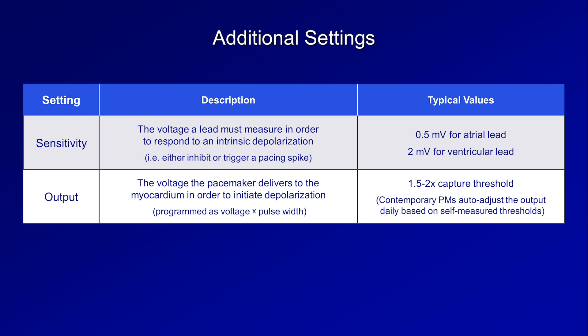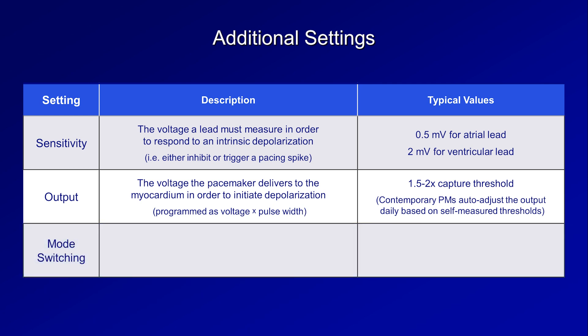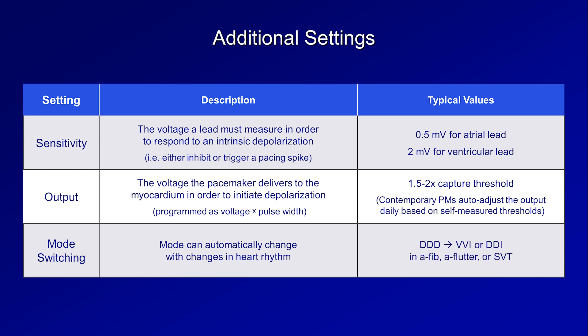The last additional setting of note is mode switching — a collection of settings that determine when the pacing mode should automatically switch from one to another with changes in the heart's intrinsic rhythm. For example, in a particularly common mode switch, a pacemaker in DDD mode will switch to either VVI or DDI if sinus rhythm were to convert into atrial fibrillation, atrial flutter, or another supraventricular tachycardia, in order to prevent extreme ventricular rates.